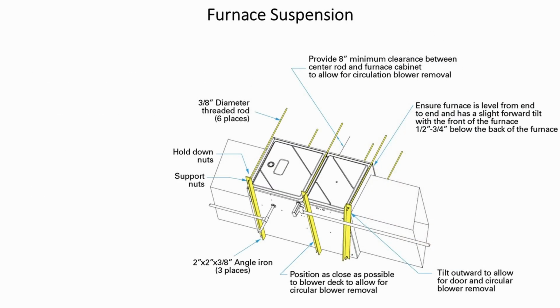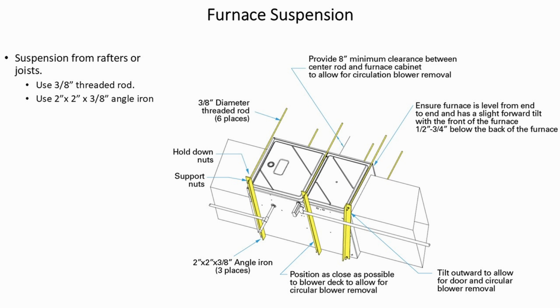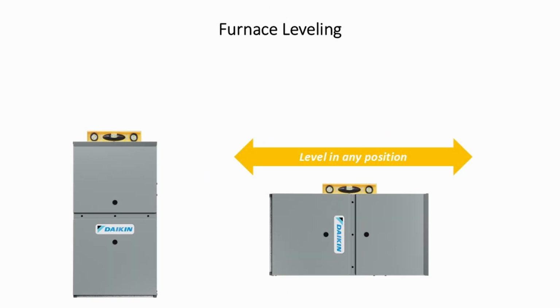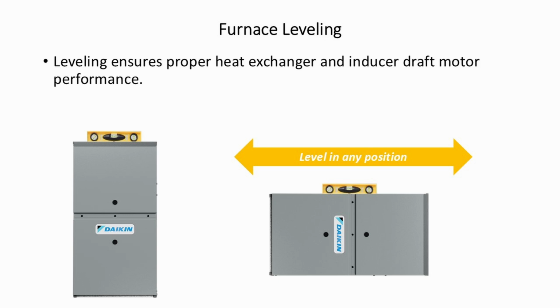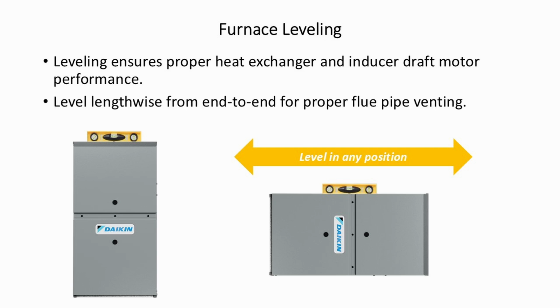Furnace suspension. For suspension from rafters or joists, use 3/8-inch threaded rod. Use 2-inch by 2-inch by 3/8-inch angle iron. Length of rod will depend on the application and the clearance necessary. Furnace leveling. Leveling ensures proper heat exchanger and inducer draft motor performance. Level the unit lengthwise from end to end for proper flue pipe venting.